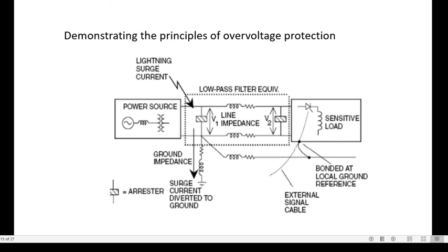These surge arrestors should have a low impulse ratio so that a surge incident on a surge arrestor may be bypassed to the ground instead of passing through the apparatus. And what is that impulse ratio? Impulse ratio is equal to impulse breakdown voltage divided by the peak value of the breakdown voltage. Okay. So this is all about the transients.